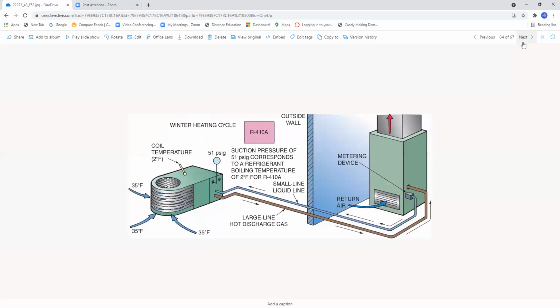Okay, this shows the winter heating cycle utilizing R410A. Look at the pressure temperatures we talked about this morning in the PowerPoint. Notice I got a 35-degree temperature going here. I'll bet you this coil is already starting to frost up by looking at this illustration. Suction pressure of 51 psig corresponds to a refrigerant boiling point of 2 degrees Fahrenheit for R410A. And notice that in this case, this is acting as our extractor for heat from the outside air. And of course, that heat is being brought in and sent up through the ductwork. Remember, when these heat pumps are operating correctly and they're charged correctly, typically we're going to get a supply temperature of close to 100 degrees.